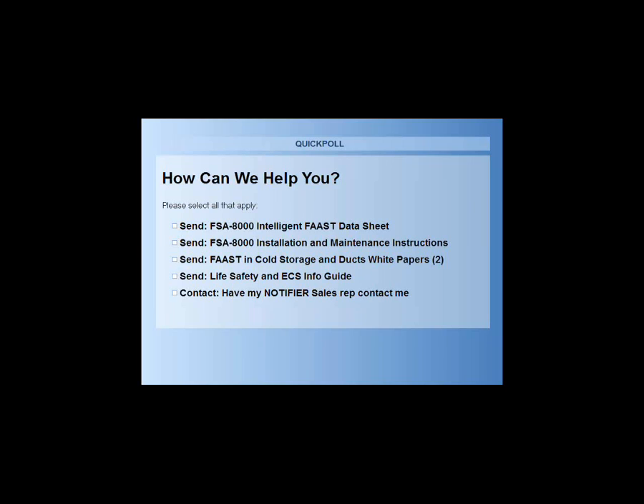You've addressed the address question. Let's see. They wanted you to elaborate on the cooperative detection. You had that, I think, as a slide that something was not included. It sits on the SLC loop, but it doesn't allow participation for cooperative detection, so you couldn't take any of the detector addresses associated with Intelligent FAAST and program it for cooperative detection with standard addressable spot detection.